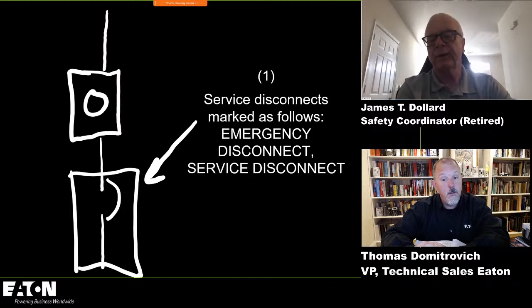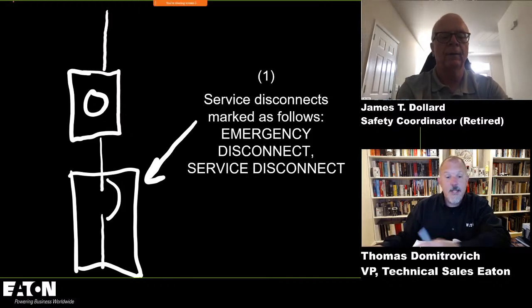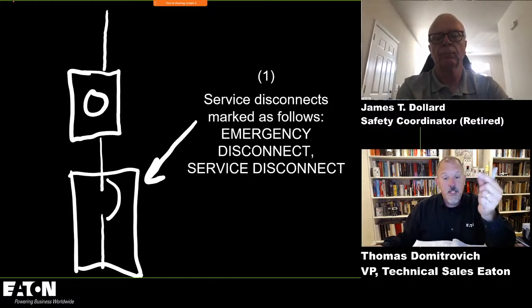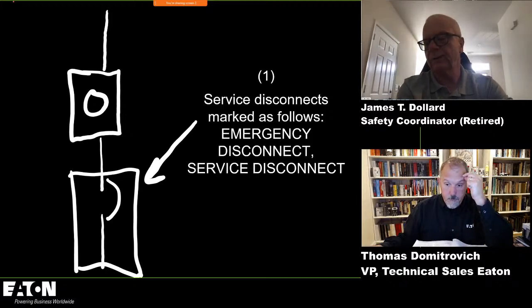Yeah, some areas of the country, for example, in the Phoenix area, driving around, you saw all of your service equipment outside, so they don't need to do anything. It's already done. They just need to make sure it's labeled properly. So if you have your outside service, you would have to label that service with emergency disconnect, service disconnect. Yeah, because it's actually two things. It's your service disconnect, and the firemen can look at it and they know that when they open that, they remove the service to the building.